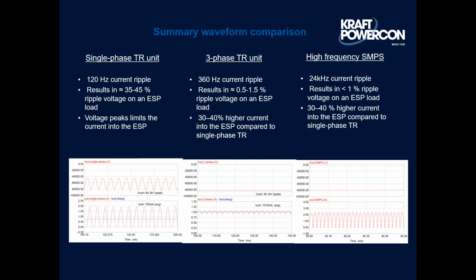The SMPS isn't a complicated piece of equipment, but it's complex to work on. For example, with a single phase or three phase TR set, at 2 a.m. a shift electrician gets called to check the precipitator. He changes the controller and SCR on the firing board and control cabinet, fixing 90% of the problems in 30 minutes, then goes home. The high frequency power supply is more advanced and takes more troubleshooting, it's not just a couple boards that fix 95% of problems, and replacing components can take longer. So these are things to consider depending on the resources you have to maintain the precipitator.